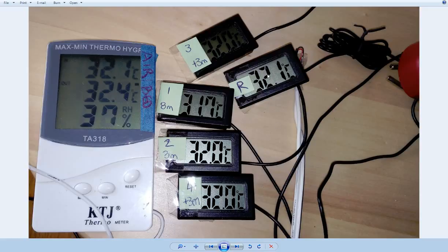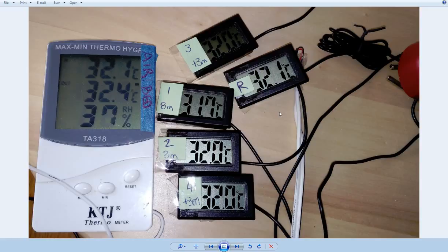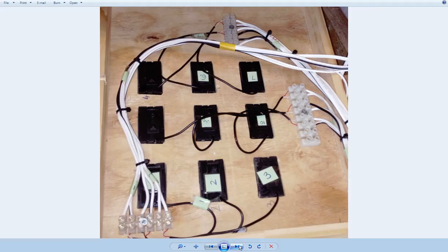Then I read how many degrees difference there is between them. What I found was a 10 meter or 30 feet extension would only reduce the reading on the thermometer by 0.3 degrees. I had to do one like that, and one was a bit shorter. Then I did a fair few that were 3 meters long, and that's only a 0.1 degree reading difference that it gives you by putting that extra cable on.